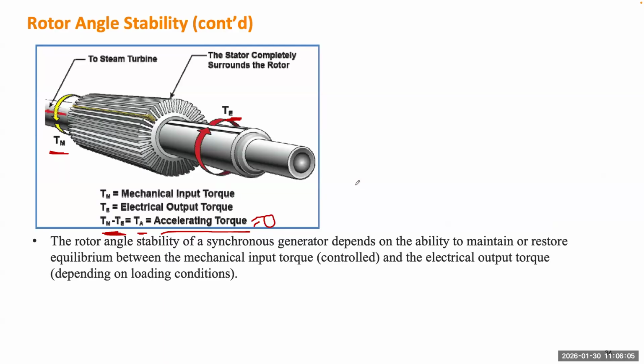So rotor angle stability is mainly about maintaining the balance between the mechanical input torque and the electric output torque. The mechanical input torque, this is the T_m, can be controlled by the governor. The operator or the engineer can control it or design a control strategy. But the electric torque really depends on the loading or the contingencies of the system, because you cannot predict what's going to happen. If you have a short circuit fault, that will suddenly reduce the electric torque. And if you don't take action and reduce the mechanical torque, the accelerating torque will go up and the system will become unstable.